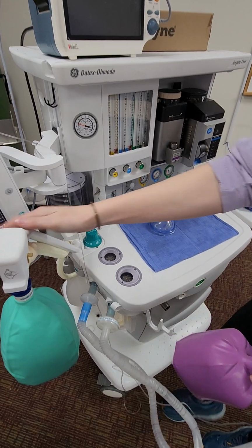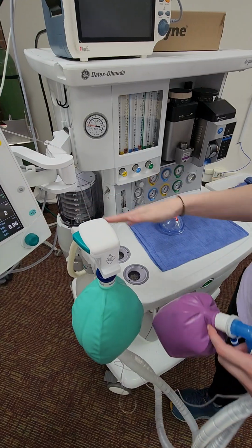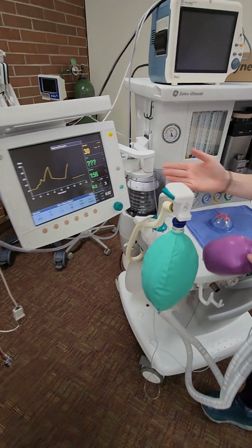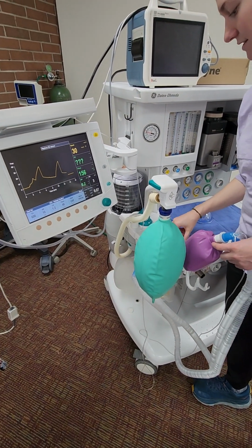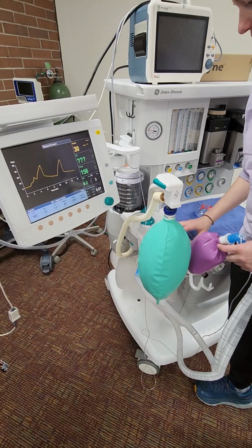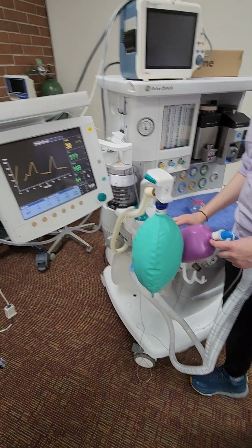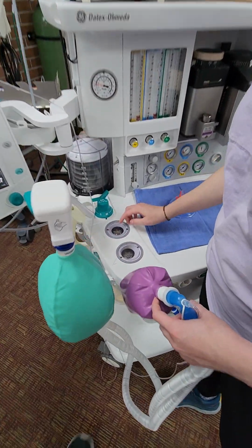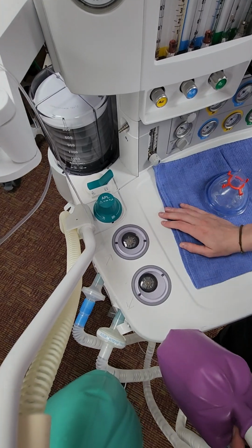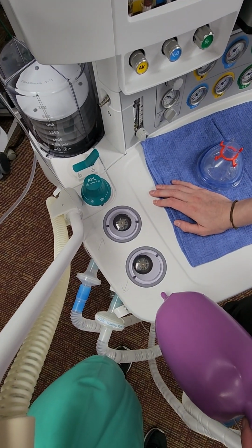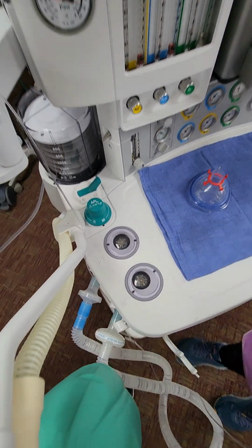And then you can verify settings again here and make sure your vent is delivering what you think it is. You'll also check these unidirectional valves, make sure they flutter at appropriate times. So flutter inspiration, expiratory valve flutters on expiratory. So once those are checked, you're good to go.